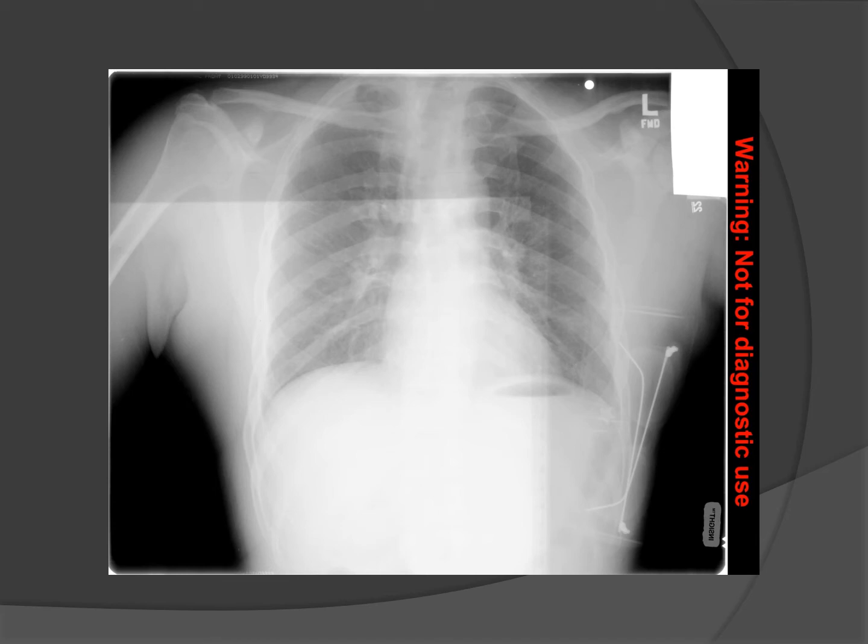First, if you look over here, you can see the patient's glasses case and their glasses within it. There's their glasses. The second thing that you see is that part of the image is a little bit darker than the rest and part of it is lighter. You notice a very distinct line here and down to here. What's happened is it looks like this image receptor was left in the room with another image receptor in front of it when another exposure was made.